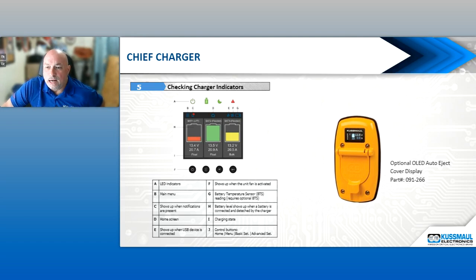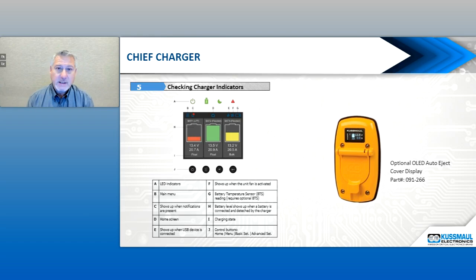Does the Chief automatically adjust each bank to bulk, absorption, or float based on the battery bank's needs? Talk a little bit about the adjustability there, Jeff. Yes, the Chief Charger will charge each bank individually. So if one bank of batteries is very low, it will charge that differently, at a different bulk, absorption, or float than the other outputs, so the other banks. They are all three independent. The only thing that ties any together is bank 2 and bank 3 must have the same chemistry. But as far as charging, yeah, you can have dead batteries on bank 2, full batteries on bank 3, and batteries that are slightly full on bank 1, and the charger will know, and it's going to charge those differently.